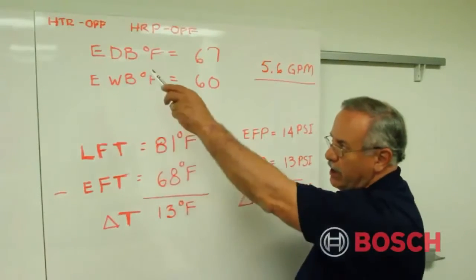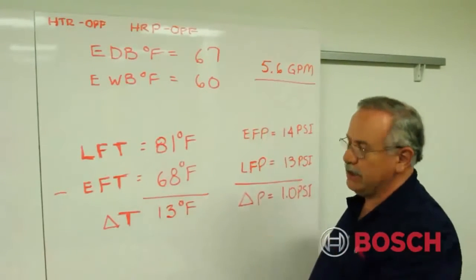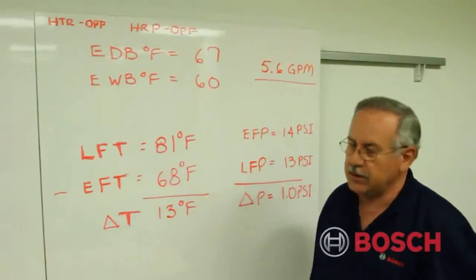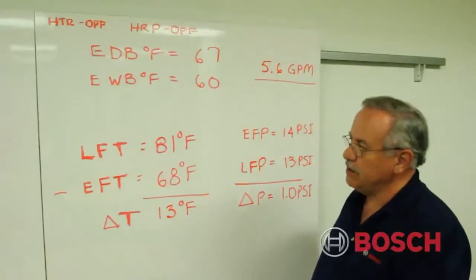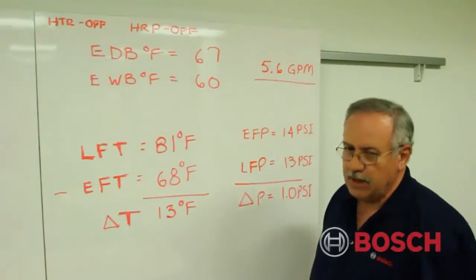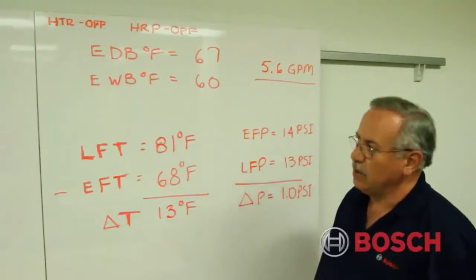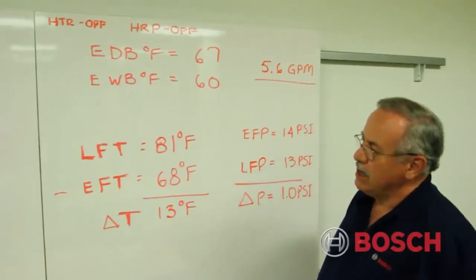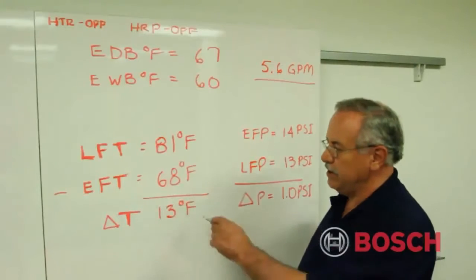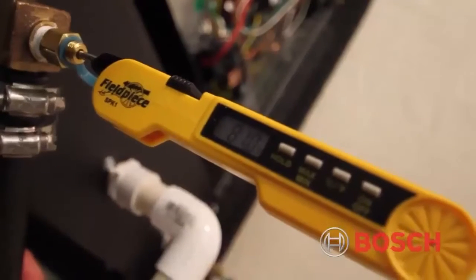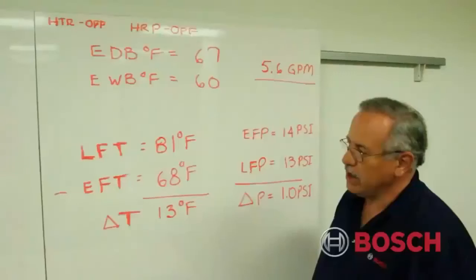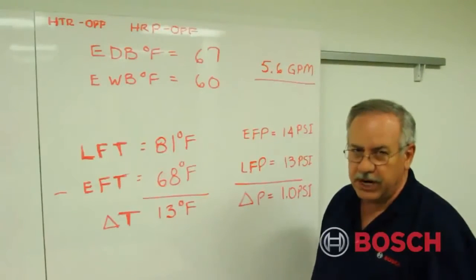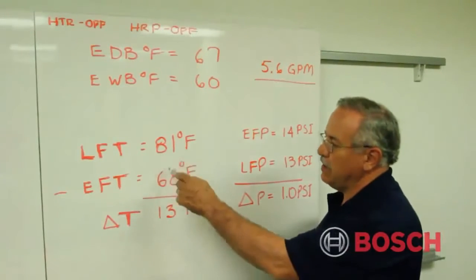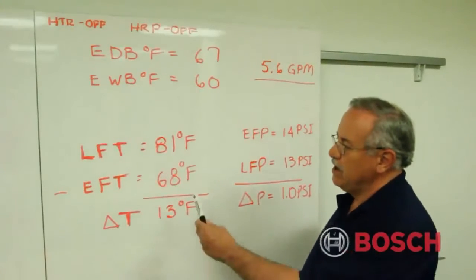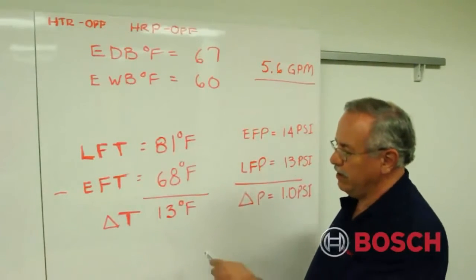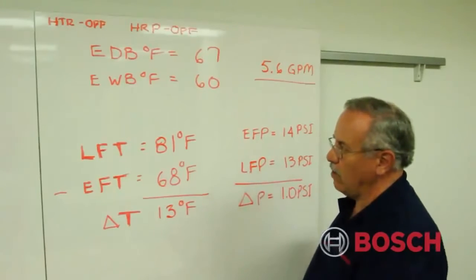We want to make sure that any electric heaters are off, as well as any heat recovery package, commonly referred to as the desuperheater. All of these must be in the off position. What Mark has found by taking the PT ports, or pressure temperature ports, on the coaxial entering and leaving, he has determined that the entering fluid temperature is 68 degrees. He's also determined that the leaving fluid temperature is 81. As we're talking about cooling, we're absorbing heat from the structure and rejecting it to the earth. So the temperature should be getting hotter when it leaves the coaxial. So here we have a delta T of approximately 13 degrees. That's one of the three factors we're looking for.